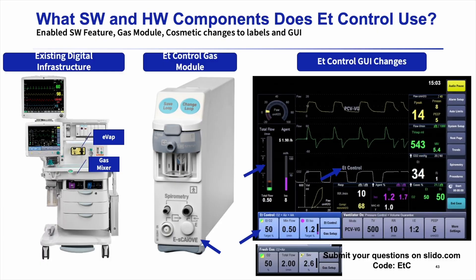What software and hardware components do we use? One of the best things about this is it uses the existing digital infrastructure of an Aisys CS2. On an Aisys, the software controls the anesthetic agent and the fresh gas — your oxygen — so there's not a lot of hardware changes needed. Aisys had all the technological capabilities to do this. The only hardware change needed is a different gas module, where that letter E on the end is related to a safety check we run for ET control. On the software side, there are a couple of visual indications on the screen when you're in end-tidal control: a waveform message, quick keys on the bottom left turn fluorescent blue, and the split screen changes as well. There's still not too much of a jump to learn how to use this.